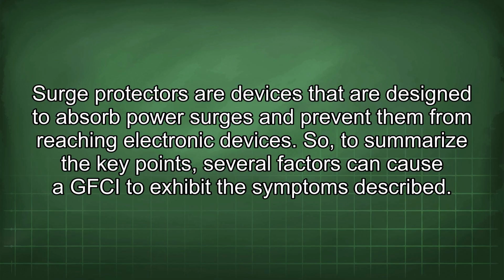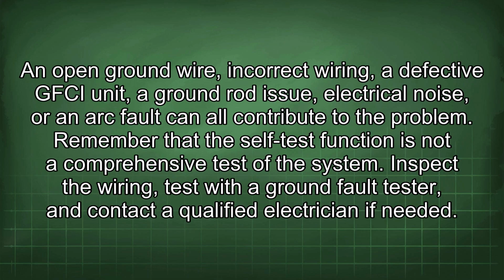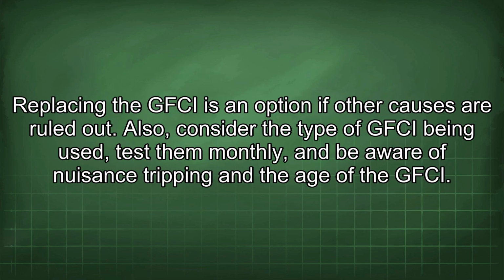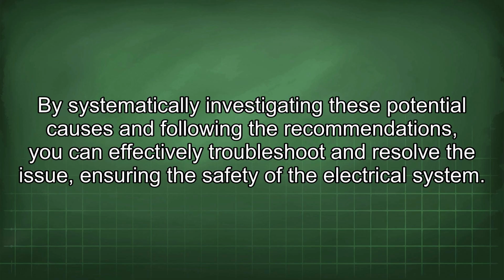So, to summarize the key points, several factors can cause a GFCI to exhibit the symptoms described. An open ground wire, incorrect wiring, a defective GFCI unit, a ground rod issue, electrical noise, or an arc fault can all contribute to the problem. Remember that the self-test function is not a comprehensive test of the system. Inspect the wiring, test with a ground fault tester, and contact a qualified electrician if needed. Replacing the GFCI is an option if other causes are ruled out. Also, consider the type of GFCI being used, test them monthly, and be aware of nuisance tripping and the age of the GFCI. By systematically investigating these potential causes and following the recommendations, you can effectively troubleshoot and resolve the issue, ensuring the safety of the electrical system.